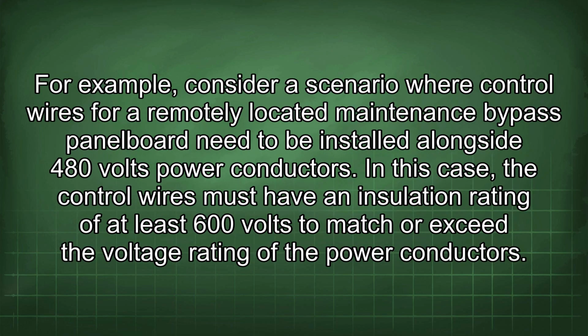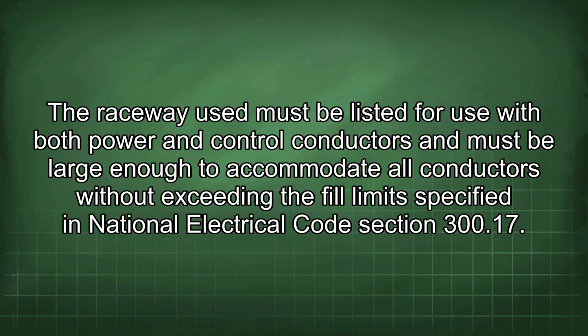For example, consider a scenario where control wires for a remotely located maintenance bypass panel board need to be installed alongside 480 volts power conductors. In this case, the control wires must have an insulation rating of at least 600 volts to match or exceed the voltage rating of the power conductors. The raceway used must be listed for use with both power and control conductors and must be large enough to accommodate all conductors without exceeding the fill limits specified in National Electrical Code Section 300.17.